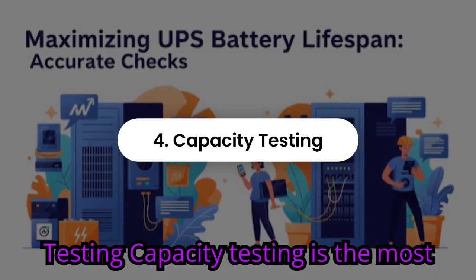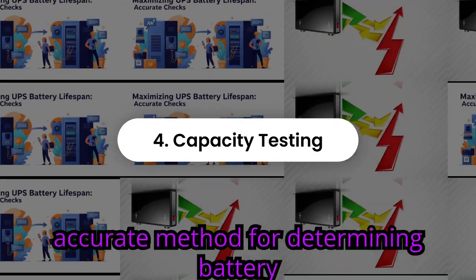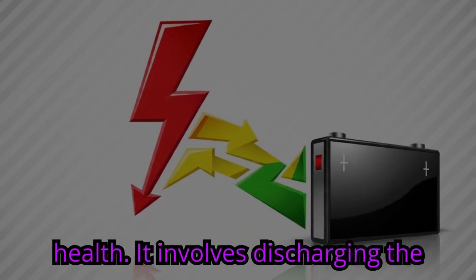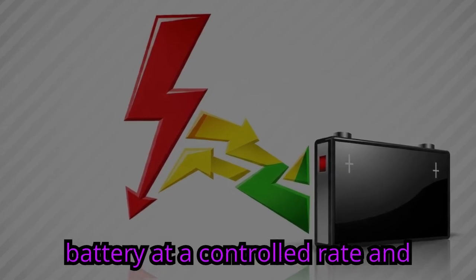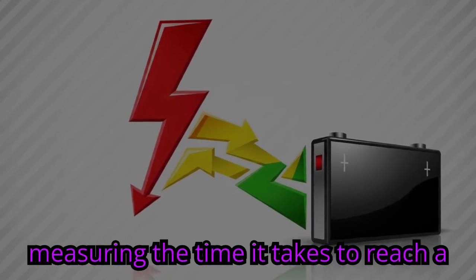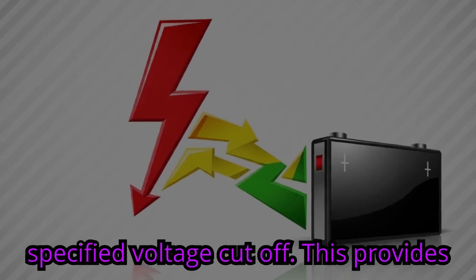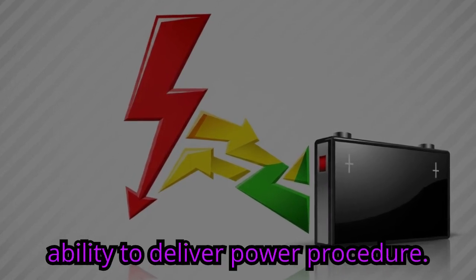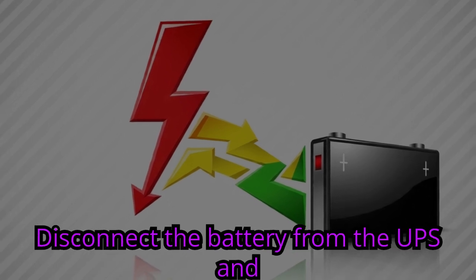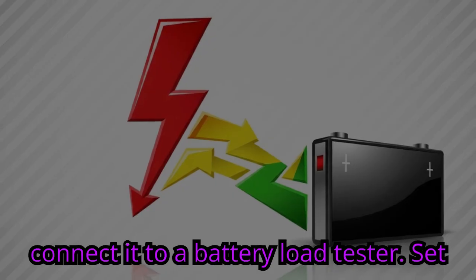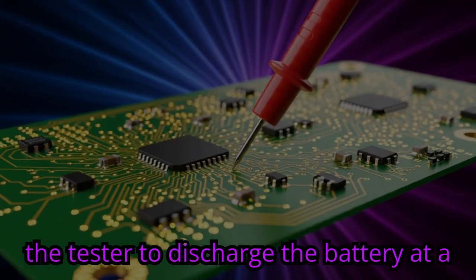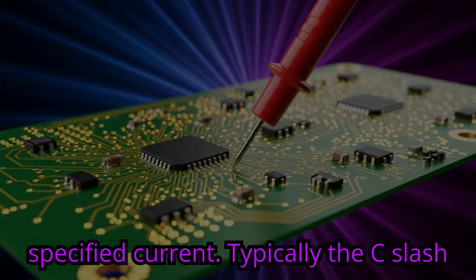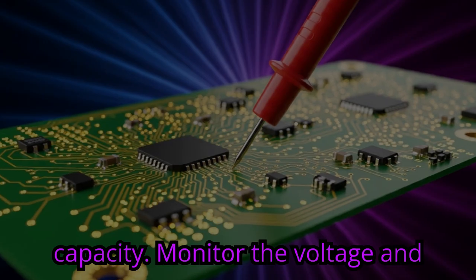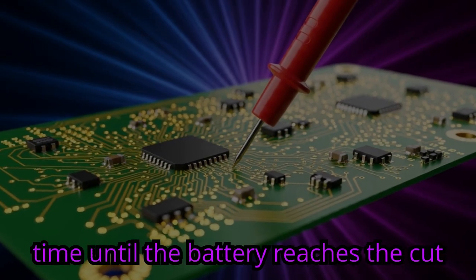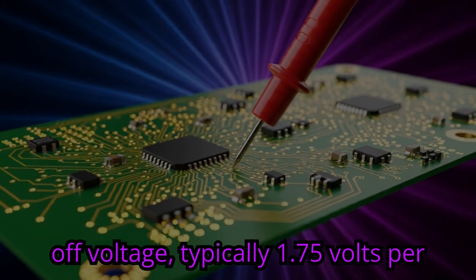4. Capacity testing. Capacity testing is the most accurate method for determining battery health. It involves discharging the battery at a controlled rate and measuring the time it takes to reach a specified voltage cutoff. This provides a direct measurement of the battery's ability to deliver power. Procedure: disconnect the battery from the UPS and connect it to a battery load tester. Set the tester to discharge the battery at a specified current, typically the C/10 rate, where C is the battery's amp-hour capacity. Monitor the voltage and time until the battery reaches the cutoff voltage, typically 1.75 volts per cell.